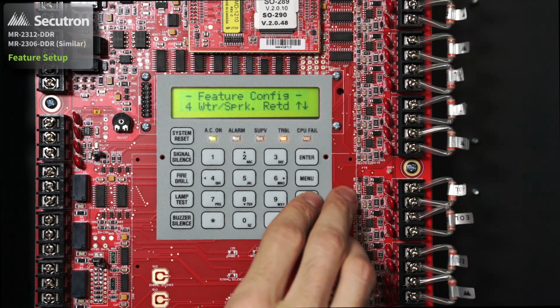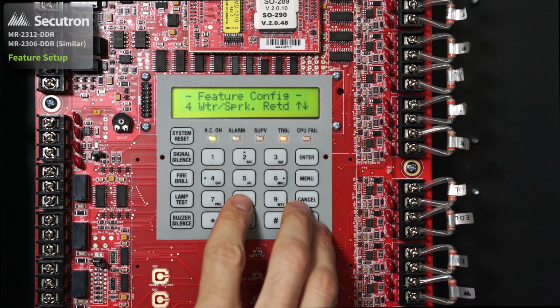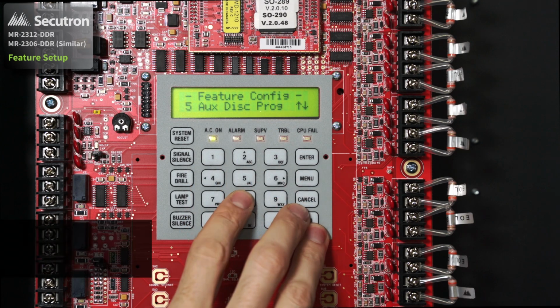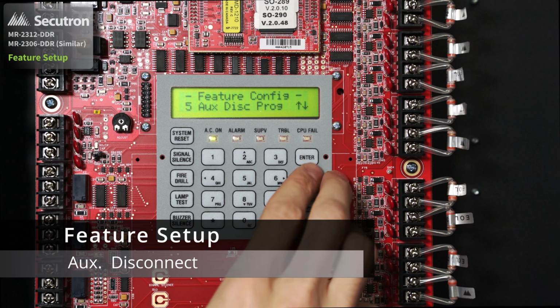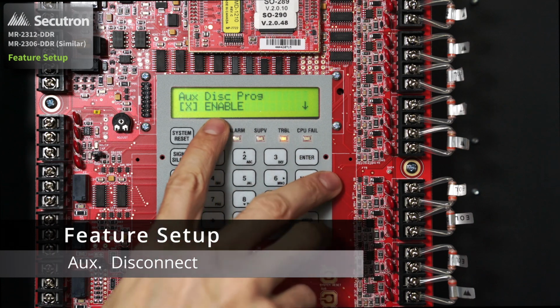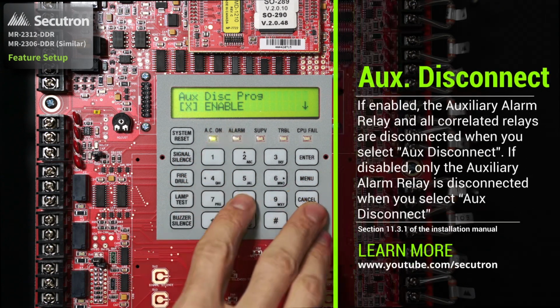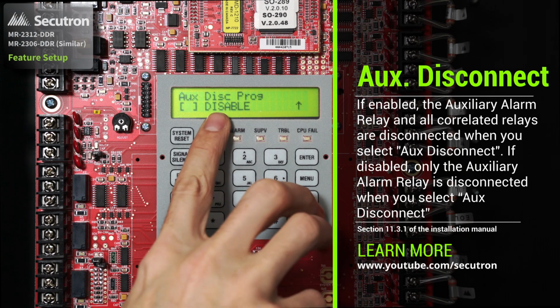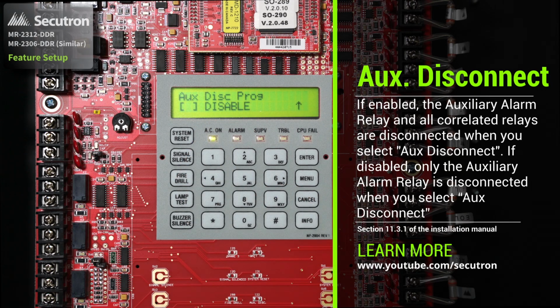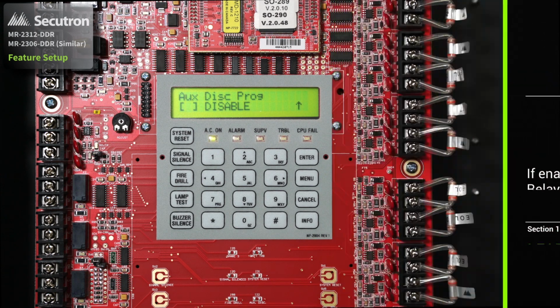We exit and go back to the features again, down to the aux disconnect programming. If we select Enter on this, again, it defaults to enabled. Or if we press down, we can disable this feature as well. If enabled, the auxiliary alarm relay and all correlated relays are disconnected when you select aux disconnect.